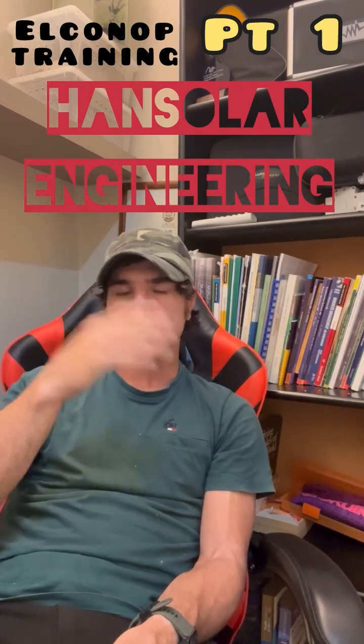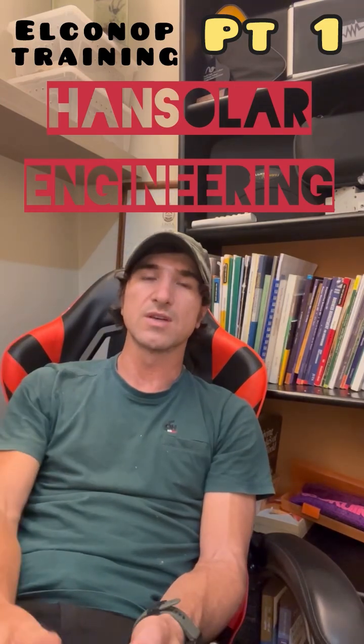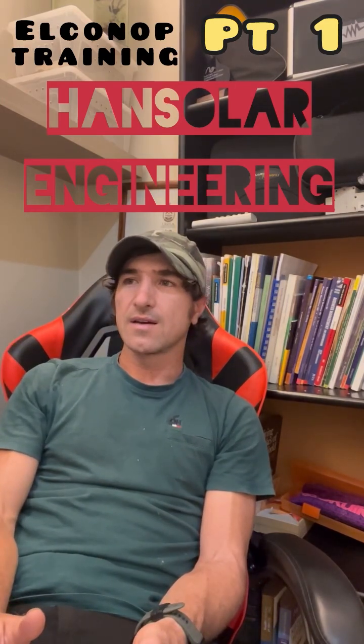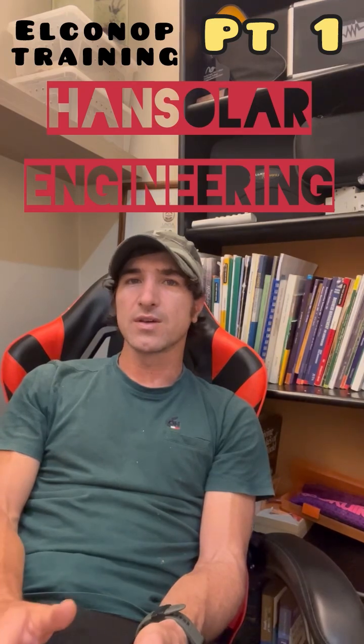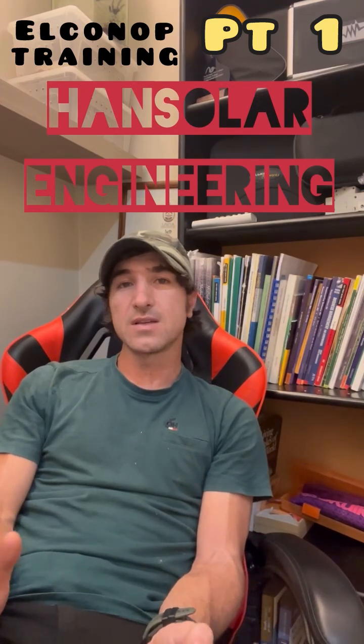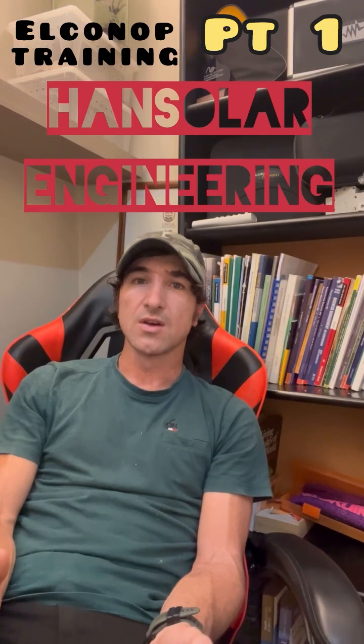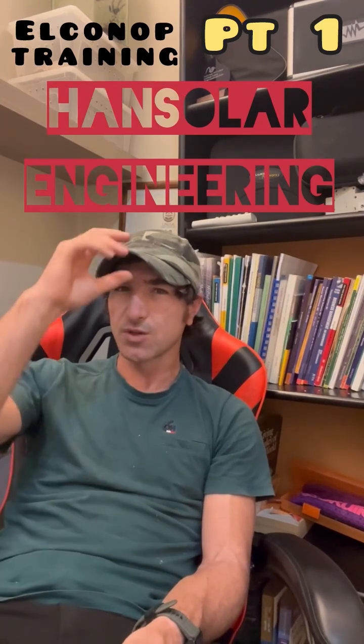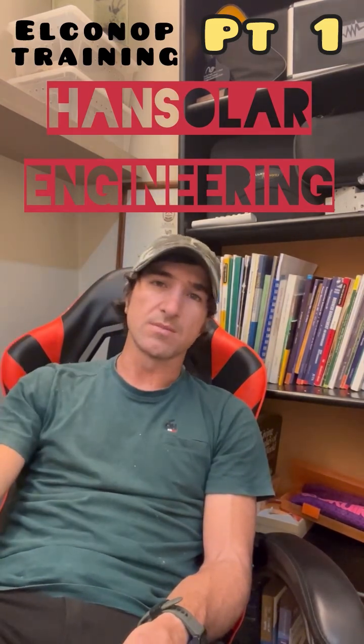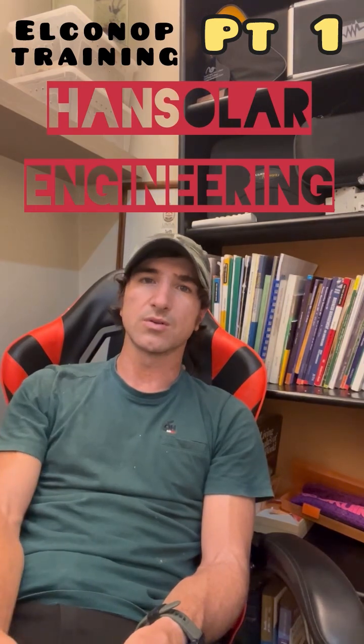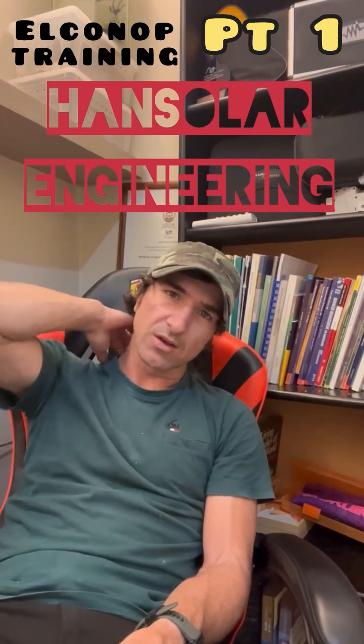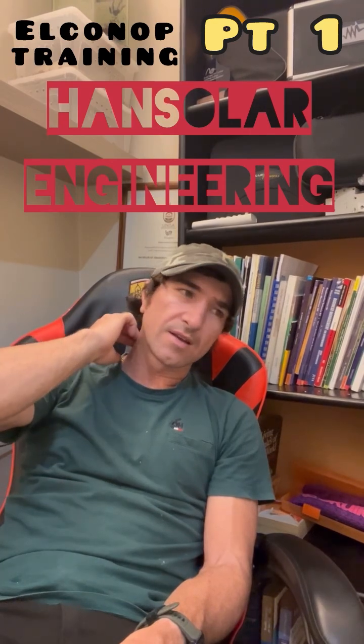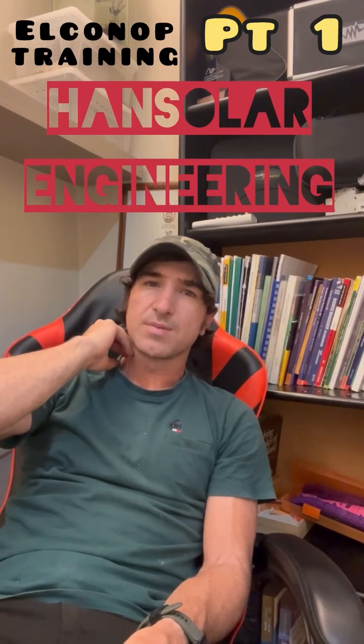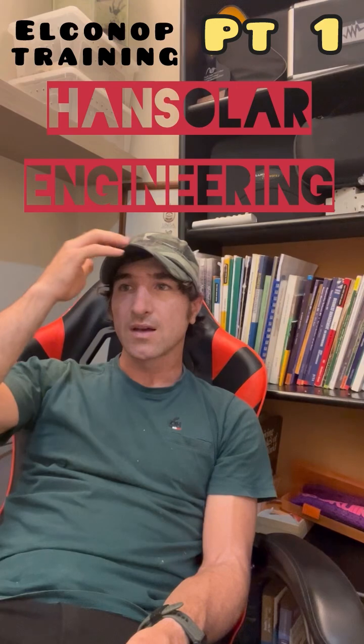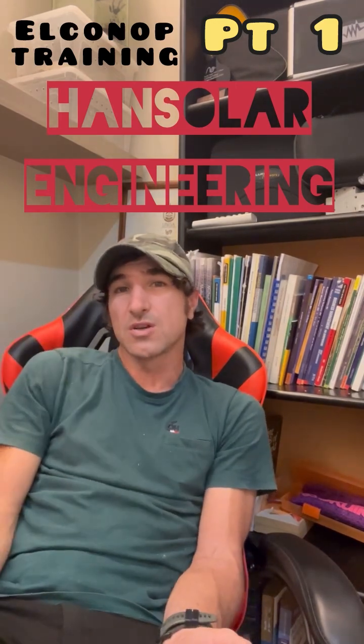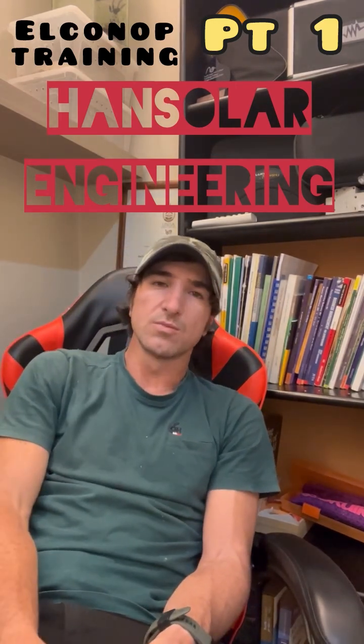The bimetallic strip cuts it out, or whatever circuit breaker you're using, there will be a delay. And basically, if it's not rated for the kA, what you test with your PSC testers will let you test what it potentially shorts at. This will not be 100% accurate, of course. It's a meter showing you what it thinks it will short circuit at. But it's pretty close. So you can size it, you can test it, and generally you want it to be larger than the PSC of your installation. There would be a safety margin. Normally a safety margin of at least 1 kA I would assume is safe.